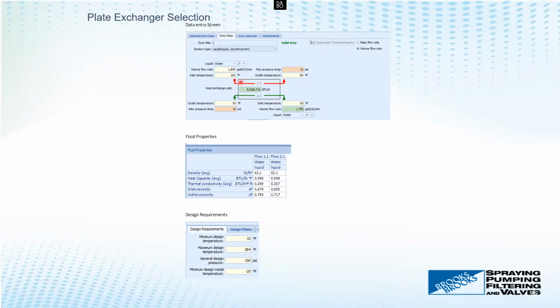What blows me away is it seems like a fairly simple application, not much heat - 10 degrees doesn't seem like much - but we're getting essentially 9 million BTUs per hour out of it. It's a tremendous amount of energy for such a run-of-the-mill application. 1,800 gallons is a lot of flow, but 9 million BTUs an hour - that's the green part of heat exchangers that continues to amaze me.